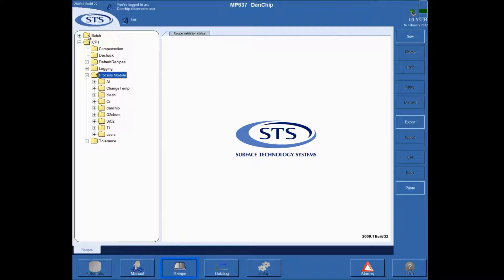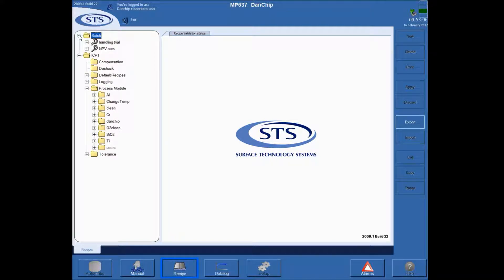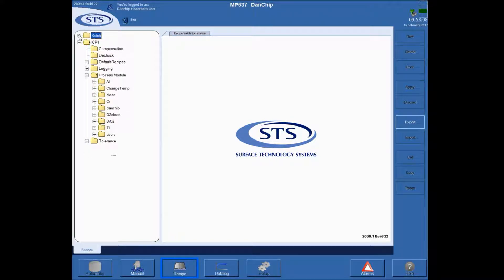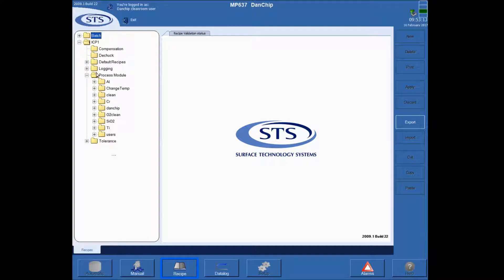In the other folder you'll find the batch recipes on the tool and they are the ones that are to be used with the cassette loader. So currently it's only the Pegasus-1 that has any batch recipes. That will be covered in a separate video.